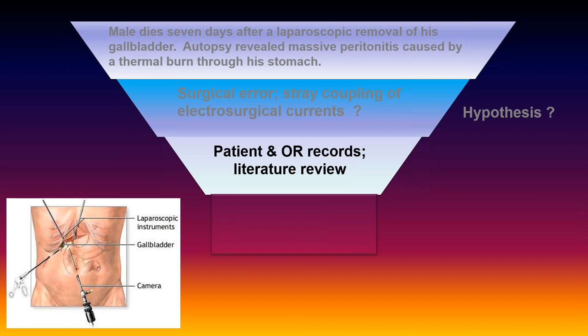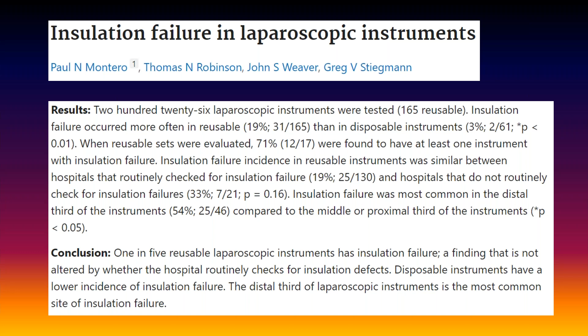And anyway, through the OR records and the literature review, I found quite a few papers that supported this, and it was quite surprising how common insulation failure in these instruments really is. I was quite stunned by it, actually. And that's exactly what ultimately happened. The insulation on these devices, especially through repeated cold sterilization, can break down, and the high open circuit voltages present during these procedures broke the insulation down. So he was getting arcing into the stomach instead of where he was operating.